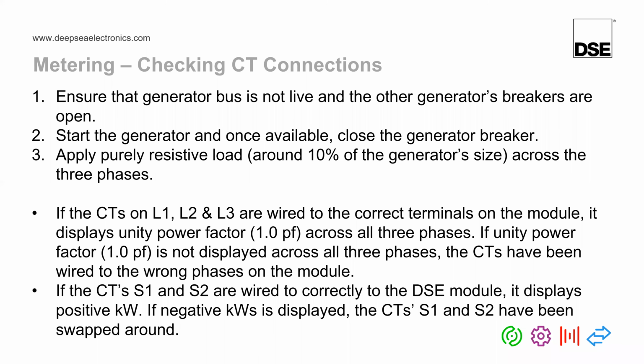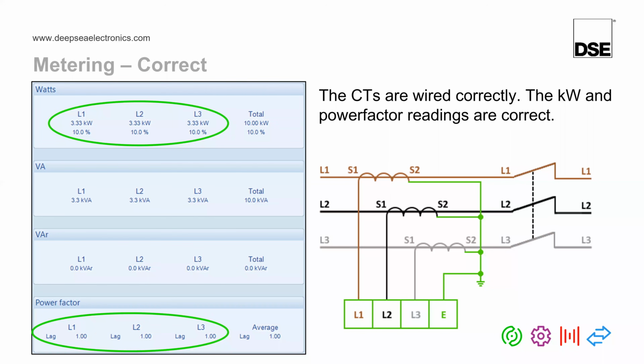So just to help explain this a little bit further, I've got these diagrams and some readings to show what we'd see if everything was correct. On the right-hand side here, you can see we've got L1, L2, L3, all wired correctly to L1, L2, L3, and the orientation of these CTs is correct. The load is on this side. We can see everything is wired correctly because the DSE module is showing the correct amount of kilowatts, the same kilowatts across all three phases, and all the power factors are at 1. So in this case, we know that everything is wired correct.